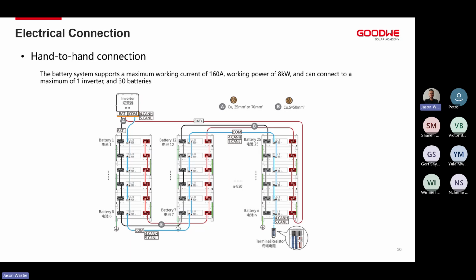Please note right at the end, we have a terminal resistor connected that terminates the communication between all the batteries, and that's what allows us to connect up to 30 of them together. Please do note that we do then have a power limit of 8 kilowatts, 160 amps of working current. So we can connect as many batteries as we need together and have a max of 8 kilowatts output through all of the batteries together.